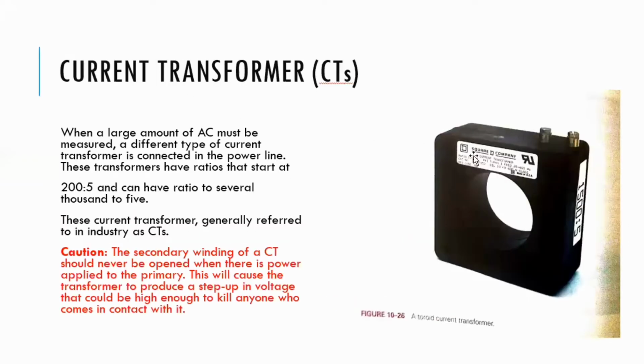There is another type of CT, which means current transformer. When a large amount of AC current must be measured, a different type of current transformer is connected in the supply line. These transformers have ratios that start at 200 to 5 and can go to several thousand to 5. These current transformers are generally referred to in the industry as CTs, the current transformer.